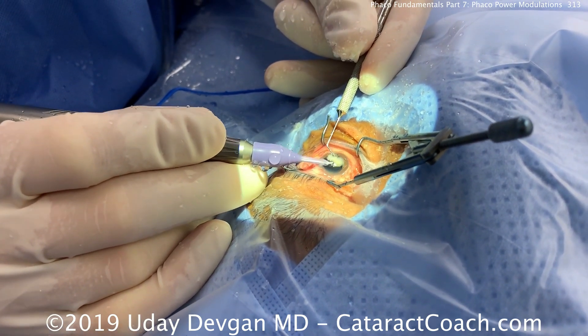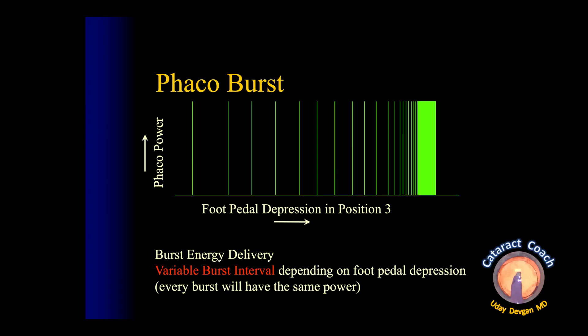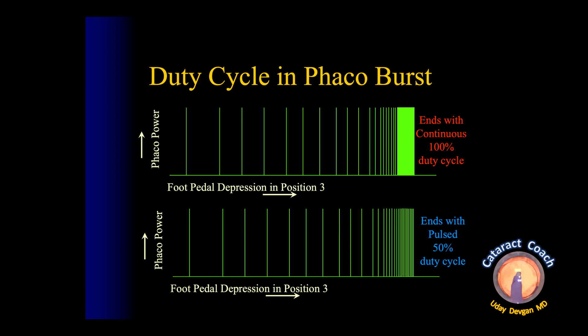Burst mode is different: every burst of phaco power is identical, and as you step on the pedal, it decreases the interval between bursts. At the beginning there are only a few bursts, then at the end the delivery becomes continuous. You can also end the duty cycle in burst mode with either continuous power or a 50% duty cycle.